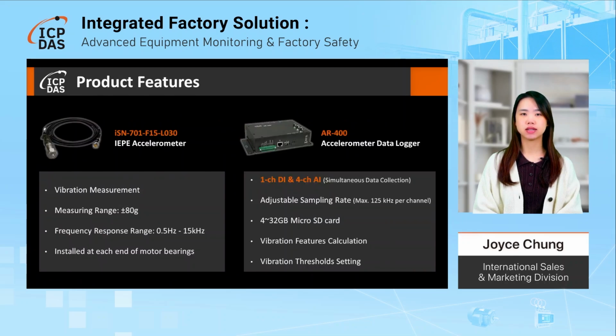The ISN IEPE accelerometer is used for vibration measurement, with a measurement range of -80 G to 80 G and a frequency response range from 0.5 Hz to 15 kHz. In this case, the customer installed an ISN 701 F15L030 IEPE accelerometer at each end of the motor bearings. Then, the collected vibration data is transmitted to the AR400 accelerometer data logger.